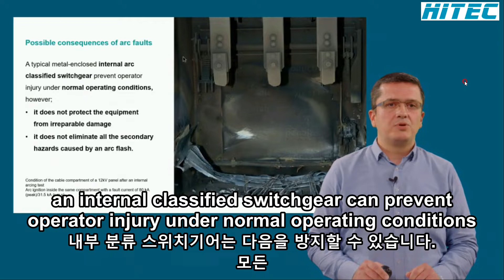An internal arc classified switchgear can prevent operator injury under normal operating conditions, which is the status where all doors and covers are closed as per IEC. But it does not protect the equipment from damage and does not prevent the occurrence of secondary hazards like pressure wave, sound blast, blinding light, fire, toxicity, contamination, etc.